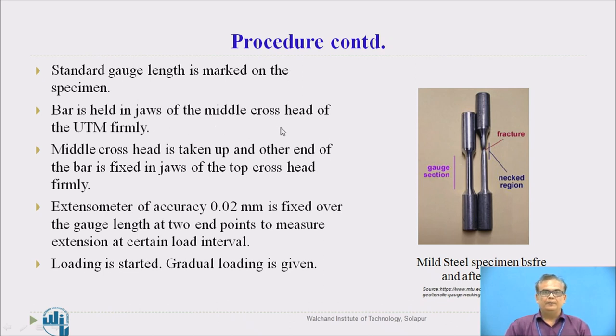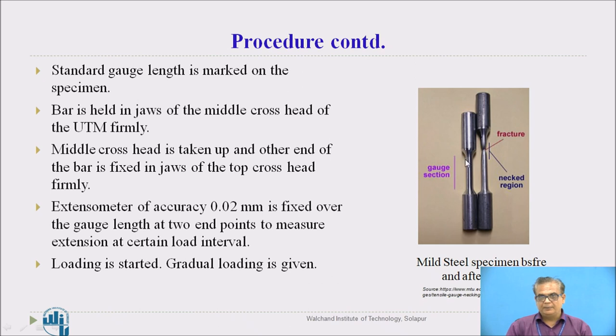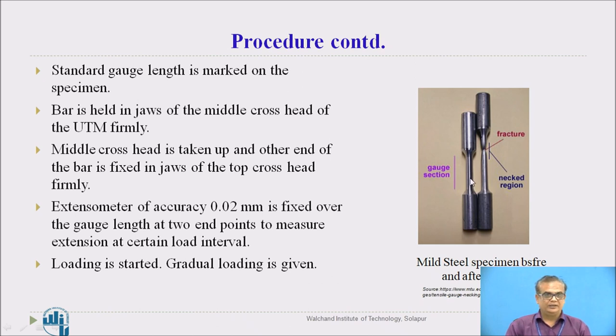The bar is held in the jaws of the middle cross head and upper cross head. First, it is held firmly in the middle cross head of the UTM. Then the middle cross head is taken up and the other end of the bar is fixed in the jaws of the top cross head of the UTM. The specimen is prepared so that its two ends have a larger diameter, while the gauge length part has a reduced diameter, to ensure failure occurs in that region. An extensometer is also fixed over the gauge length to take strain and elongation readings during testing.